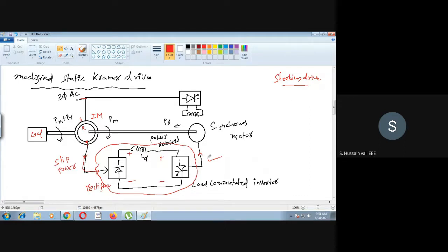In case of the Scherbius drive, it directly goes to the three-phase supply through a transformer, of course. Now here it is different. I told you the path - what is different here is that this three-phase supply goes to the synchronous motor. So this AC supply from the load commutated inverter goes to the synchronous motor.